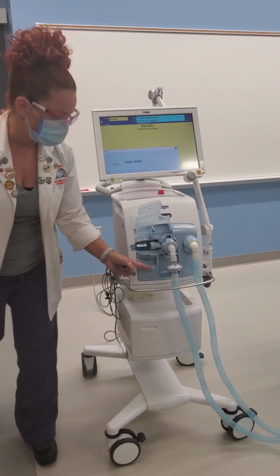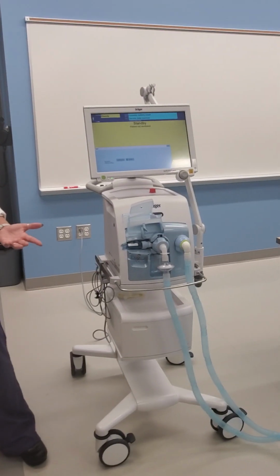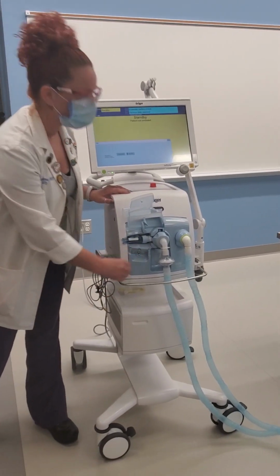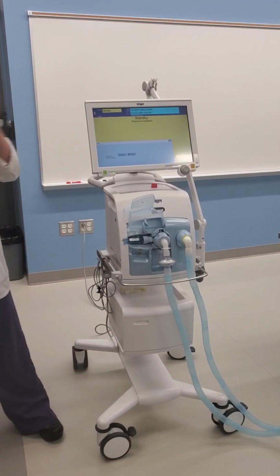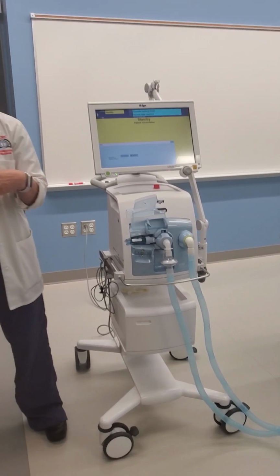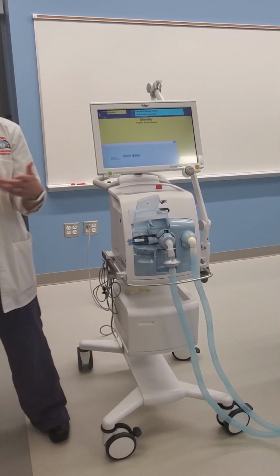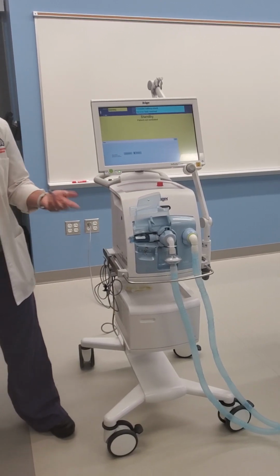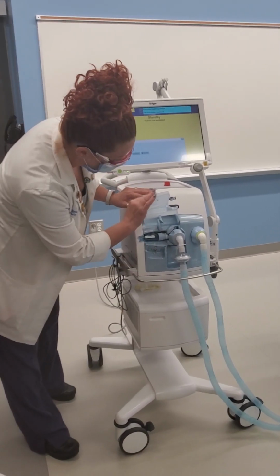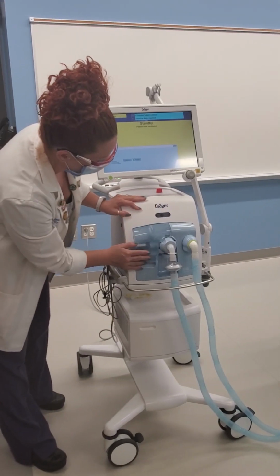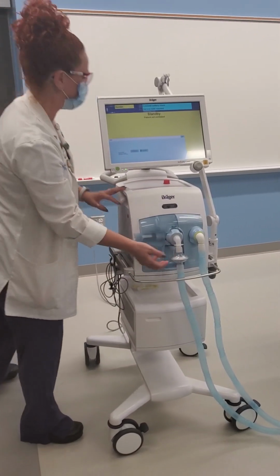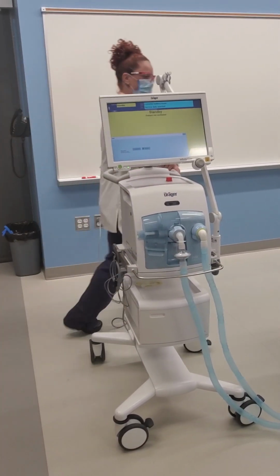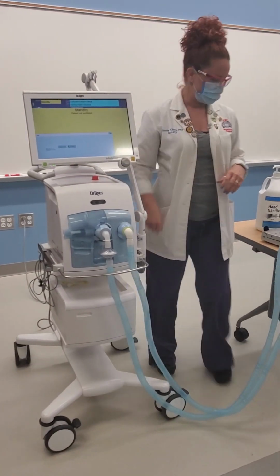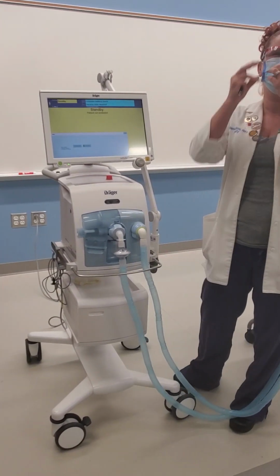What this alleviated is that fluctuation in volume, and it's only on inspiration, and you can choose how long to run it for. It's like 5, 10, 15, and then it stops automatically. Okay? So you can run a nebulizer there, flow sensor, expiratory valve. Oh, somebody switched it. I had this on the inspiratory side by accident. And I got yelled at for it.